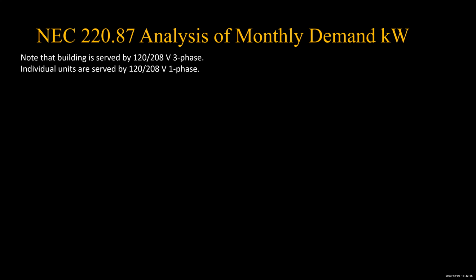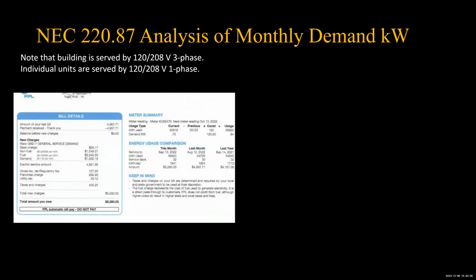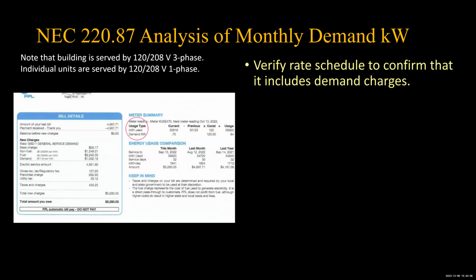We've got 120/208 3-phase. The individual units are 120/208. Here's the building's electric bill, and look what we got. General service demand, hot dog. Kilowatt hours used, demand kW. 84 kW demand, 58,920 kilowatt hours. It's the 84 kilowatt demand that we're interested in. And this happens to be the highest bill of the year, the highest demand. So what is 84 kilowatts on a 120/208 service? They're kilowatts, not kilowatt hours. So there's your demand charge right there, along with the energy charge.